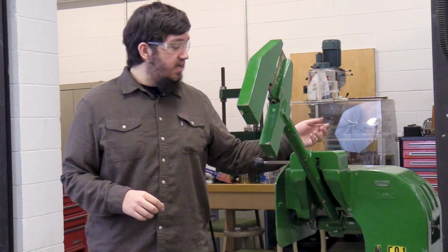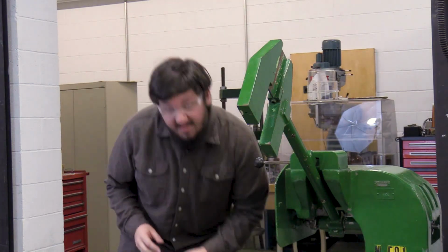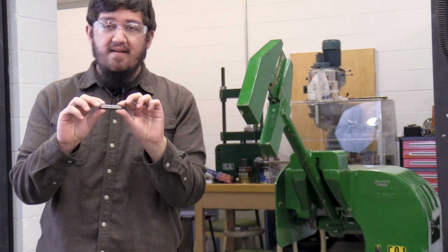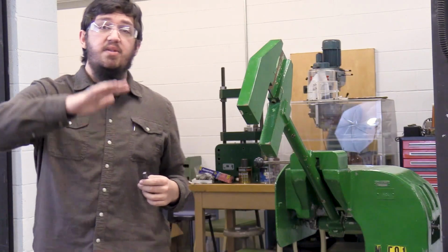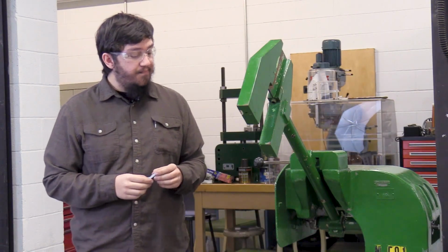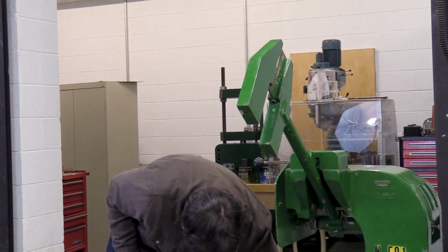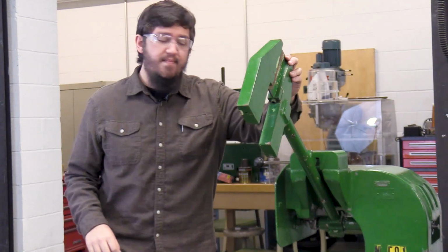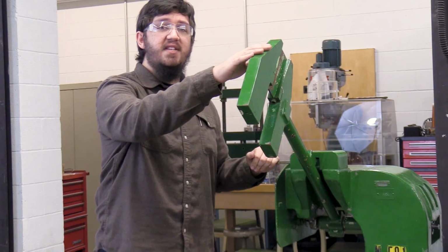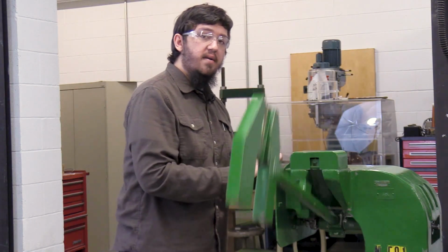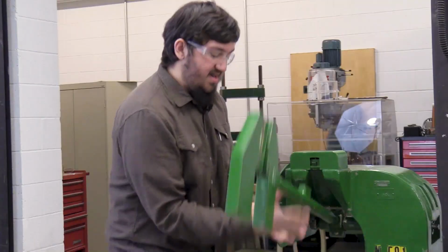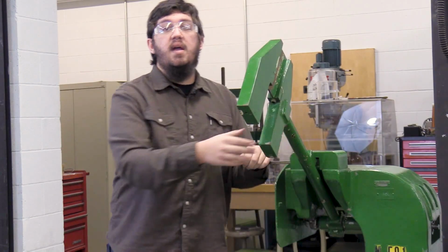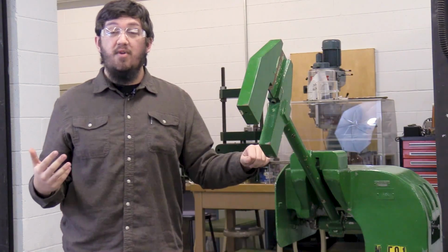What it does is we take a bar like this, and it applies a very high rate of loading. So it swings through really fast as opposed to the other machine, which is much slower. It applies that load using this head, and it measures the difference in height between before and after the part is broken in order to determine the amount of energy used to break that part.